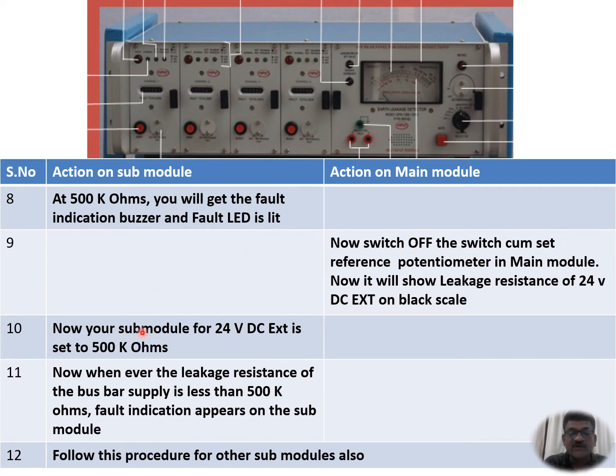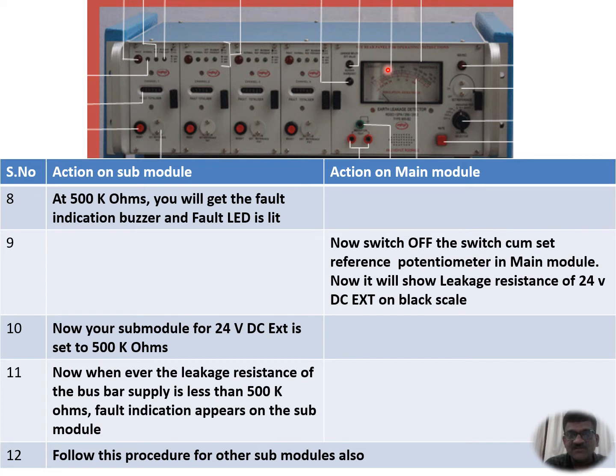Now the submodule for 24 volts external is set to 500 kilo ohms. Whenever the leakage resistance of the bus bar supply is less than 500 kilo ohms, a fault appears on the submodule. For example, if it was presently 5 mega ohms but the cable slowly deteriorates after 6 months or 1 year — more leakage or a defective conductor — when leakage reaches 500 kilo ohms and the module is also set to 500 kilo ohms, you will get the fault indication. This procedure should be adopted for all submodules.